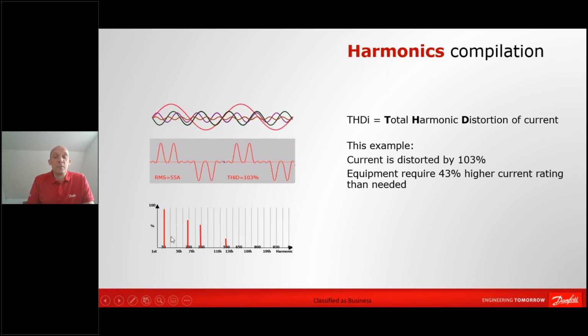Simply by adding 4 signals together, we have actually represented almost the current waveform that we wanted to represent. The order that we just added was called the 11th, so 11 times 50, 550 Hertz, is the signal frequency of that one, and you can see the amplitude went down. So you will typically see when you're talking about harmonics that the first is the highest, and then the following orders are declining, getting smaller and smaller. That's typically what you see in a system like this: the individual peak harmonics are reduced the higher the order gets.